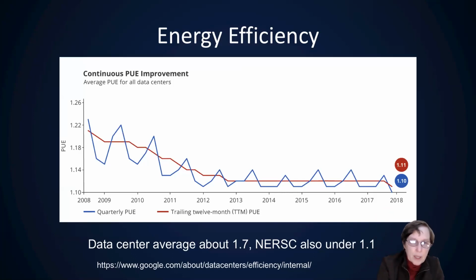PUE is the percentage of overhead power used in a data center relative to what it takes just to run the racks. You measure the total power draw for computing and storage, then look at the amount the whole building is drawing, and take the fraction over 1. A perfect PUE would mean no overhead at all, where the power drawn equals exactly what it takes to power the racks.